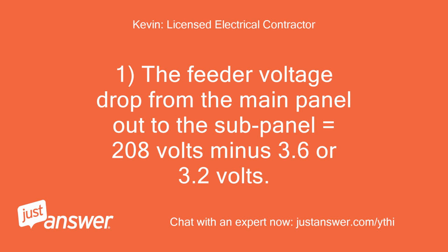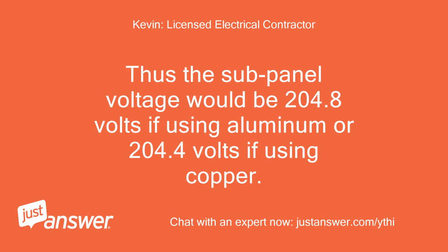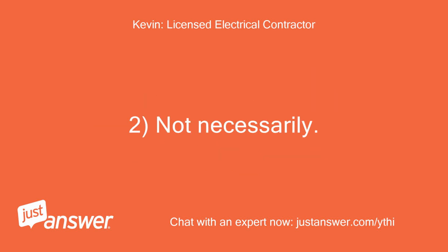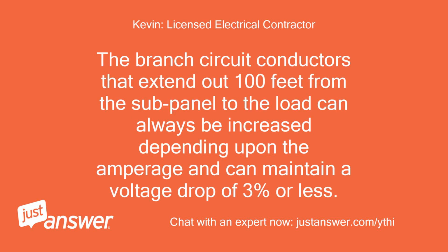1. The feeder voltage drop from the main panel out to the subpanel equals 208 volts minus 3.6 or 3.2 volts. Thus the subpanel voltage would be 204.8 volts if using aluminum or 204.4 volts if using copper. 2. Not necessarily. The branch circuit conductors that extend out 100 feet from the subpanel to the load can always be increased depending upon the amperage and can maintain a voltage drop of 3% or less.